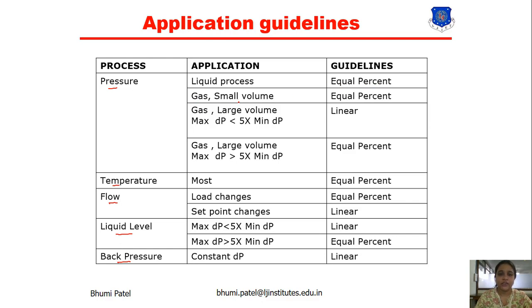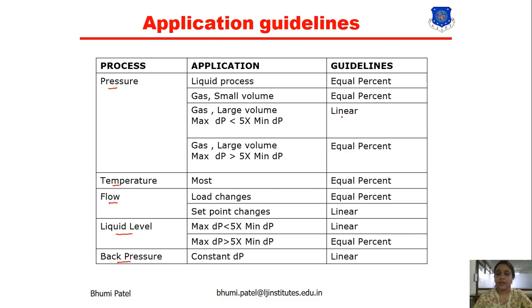For gas with large volume, where the maximum differential pressure is less than 5 times the minimum differential pressure, we must use linear characteristics. For gas with large volume where the maximum differential pressure is greater than 5 times the minimum differential pressure, we use equal percentage.